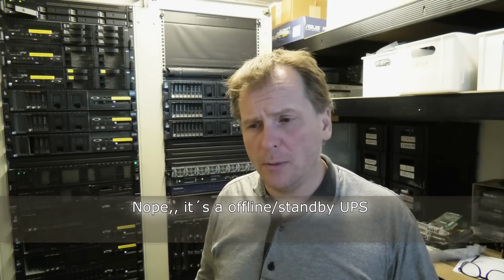I'm not totally sure about that, but the other option is a double inverting UPS, which takes the power coming in, converts it down to DC, charges the batteries, and converts it back to AC again. That means there are losses converting it to DC, and losses converting it back to AC. So double inverting UPSs are very good at ensuring stable power, but they do it at a cost - always using power for those losses, converting one way and then the other.